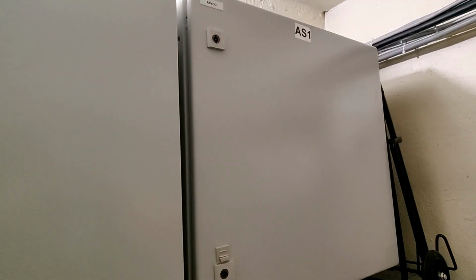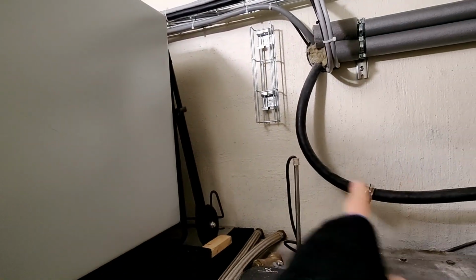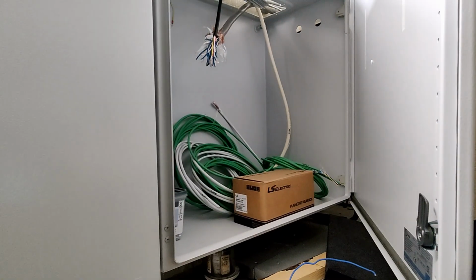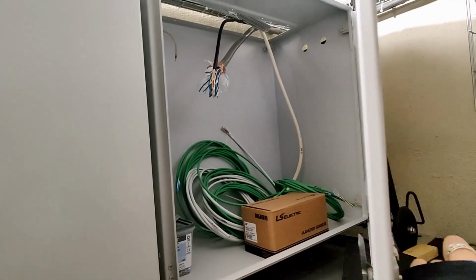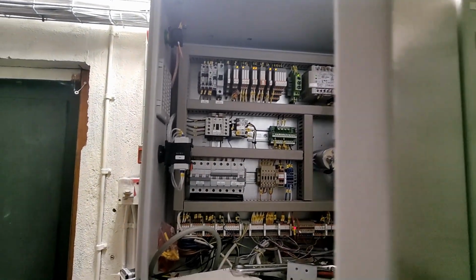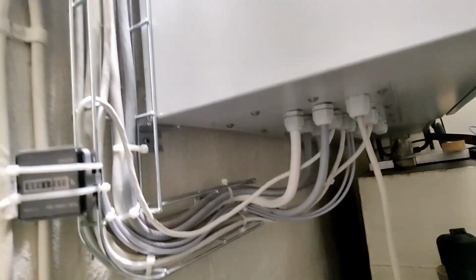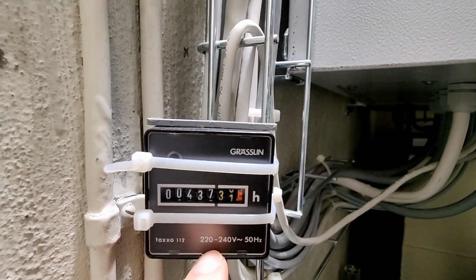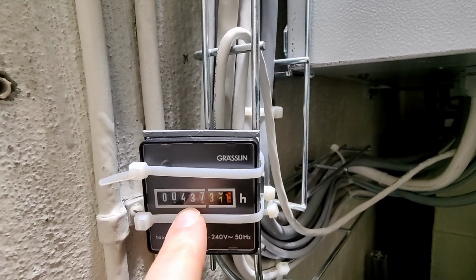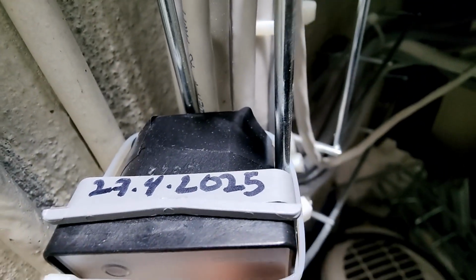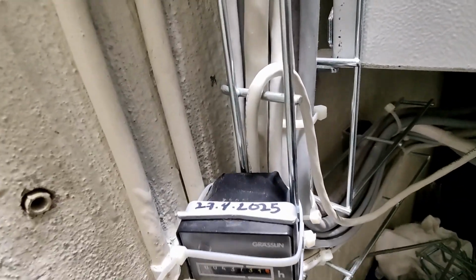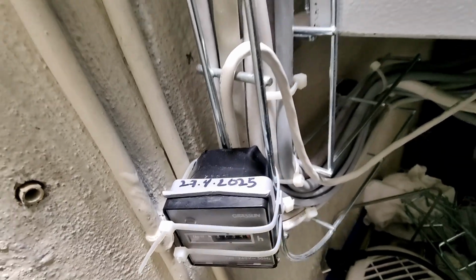And over here we have two cabinets. This one will be for the cable that comes from the bunker. It's empty at the moment. Not so much in here. And this one is for controlling the heat pump. Some cables that run to it. And this one is how long the heat pump has been running. It has run 437 hours since that date. Almost 9 months.